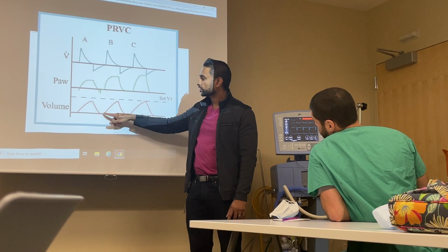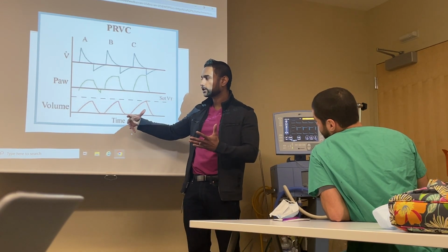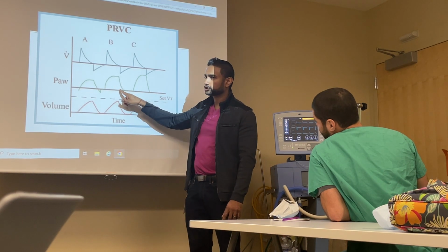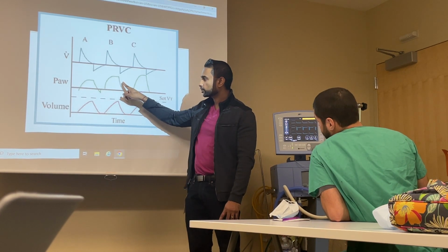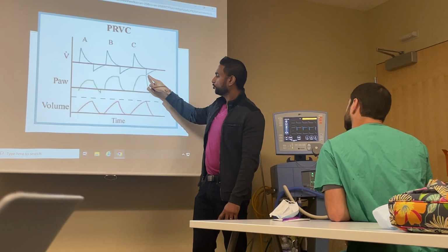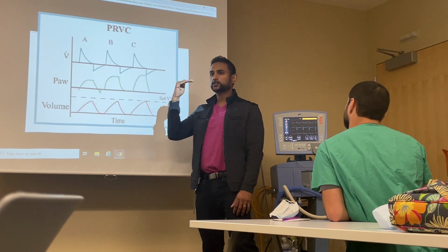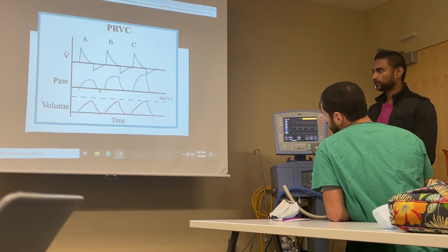Five seconds later, my next breath kicks in, guess what? Okay, I think the lungs are not that stiff as I thought they would be. I'm gonna give a little bit more pressure. Because I gave more pressure, guess what happens to my tidal volume? Slightly more elevated. Because I gave more pressure, guess what? I finally reached my target tidal line. So it detects the patient's lung compliance breath to breath, and then determines whatever the patient needs. So it doesn't go crashing hard like ACVC. Okay, all right, so we can go to the next one.